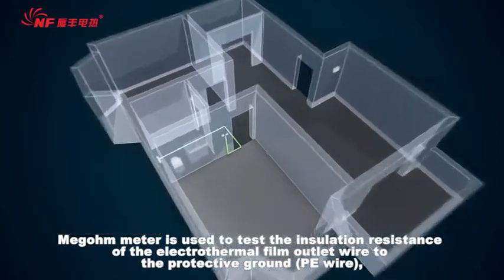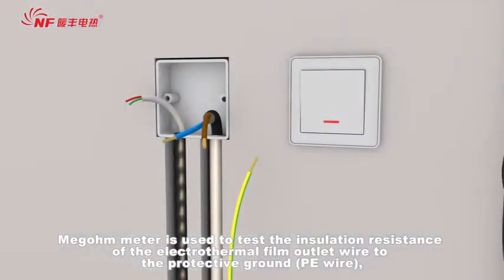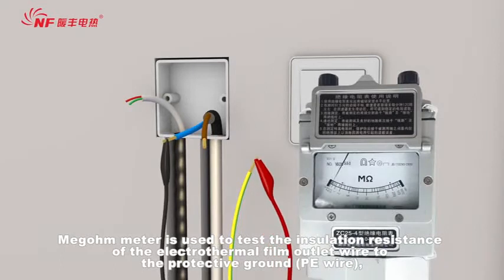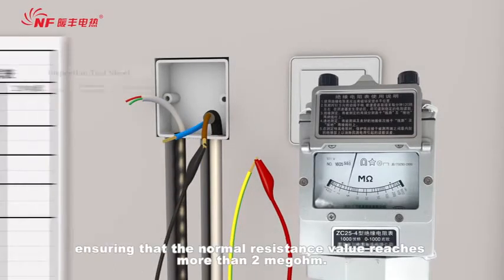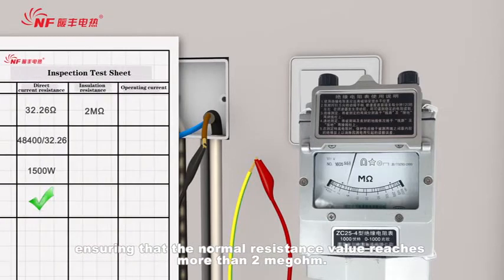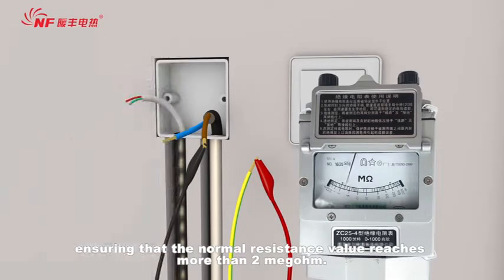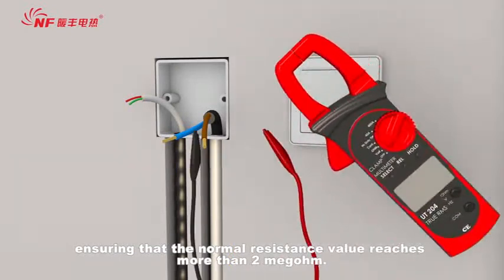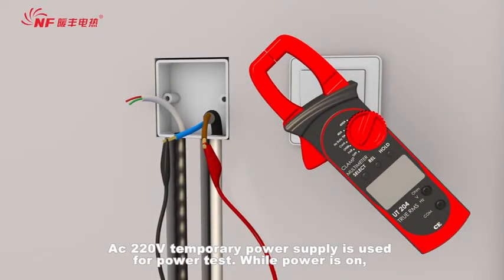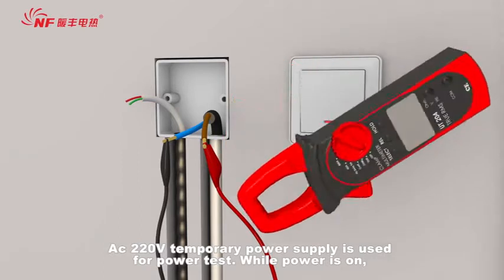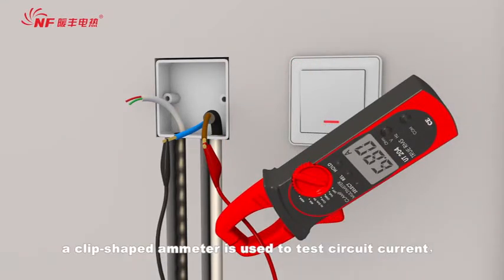Megohmmeter is used to test the insulation resistance of the electrothermal film outlet wire to the protective ground, ensuring that the normal resistance value reaches more than 2 megohm. AC 220V temporary power supply is used for power test, while power is on.